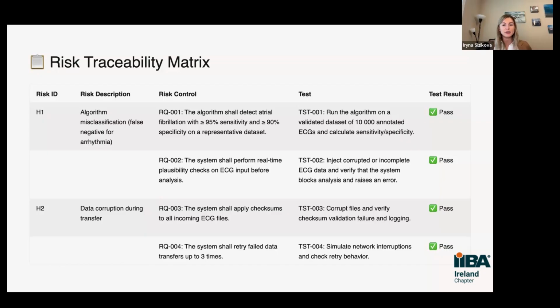Then let's see the risk controls. For hazard number 1, we have: algorithms shall detect atrial fibrillation with more than 95% sensitivity and more than 90% specificity on a representative data set. So how will the test case look? We run the algorithm on a validated data set of, for example, 10,000 annotated ECGs and calculate both parameters. If we get numbers above 95% and 90% respectively, we say that our test is successful. If not, the test fails, and then we further decide if we can go on the market with that, or we need to improve the software, or check the process, or what other measures we need to establish.